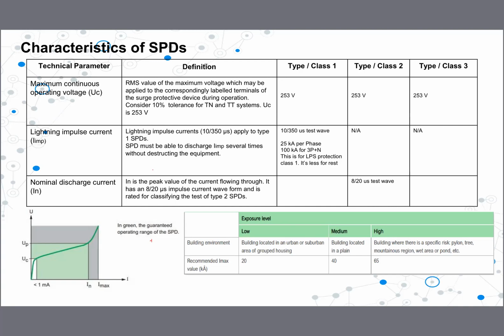When we are designing a lightning protection system, actually the design of the lightning protection system and the surge protection are different. When you are designing a lightning protection system, you need to calculate the risk level and decide what class of lightning protection you need, right? But for surge protectors, it is compulsory to install surge protection devices. It was not in the 17th edition, but it is explained as a mandatory requirement in the 18th edition of the IET. So we have to install them at different levels.